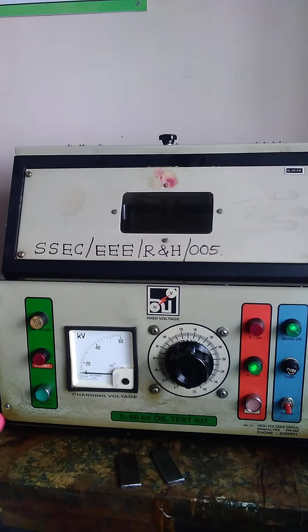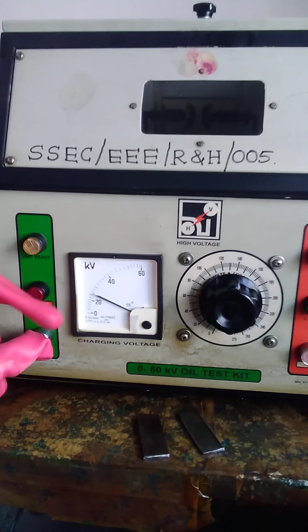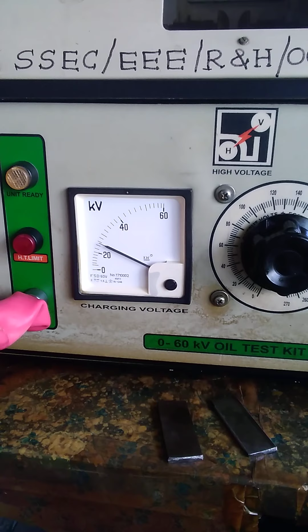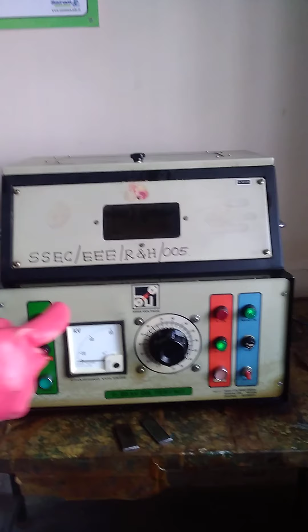The breakdown occurs between the two electrode gap. Now how can I show you? You can press this memory push button. So here it shows 0, 20 - that means 24 kV. 24 kV is the breakdown voltage.